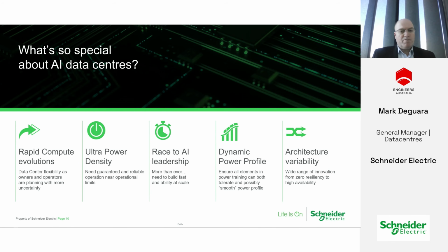Then there's the dynamic profile. If you look at a high performance compute, take the NVIDIA product for example, it's peaking at anywhere up to 1.8 times its nominal power rating. So if it's a kilowatt, it's peaking at 1.8 kilowatts. So what do I design for - the 1, or the 1.8? What impact does that have on UPSs? What impact on cooling? If I'm running on diesel generators, can a diesel generator take that overload in a short period of time? That's another impact that has to be considered.